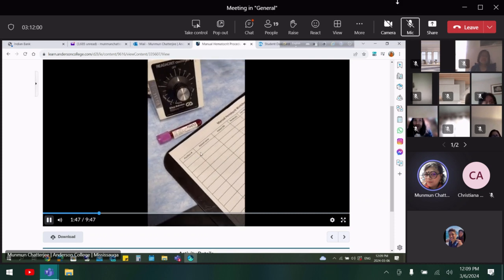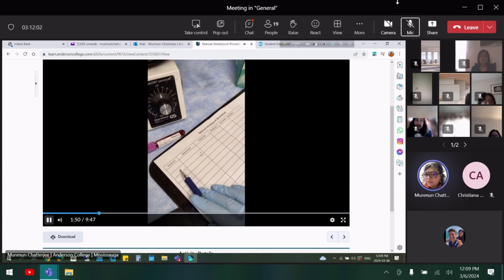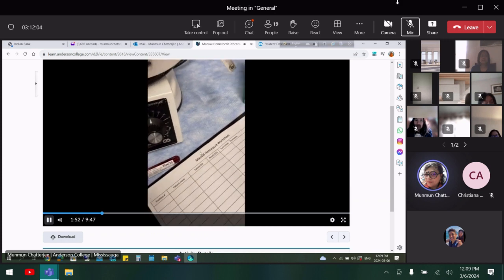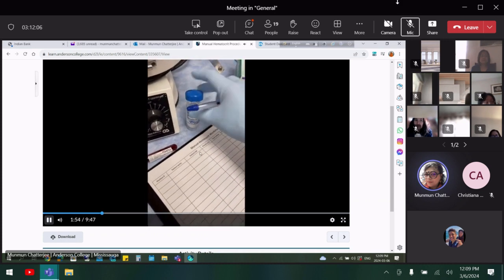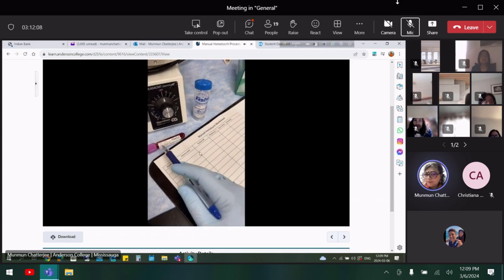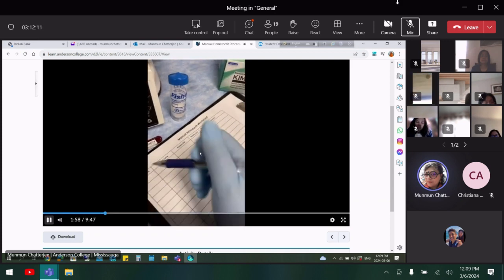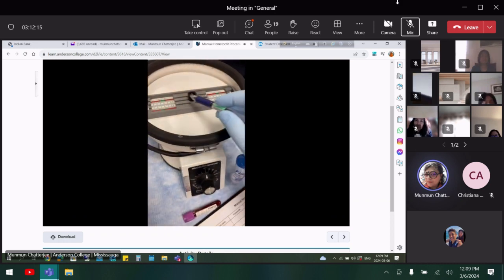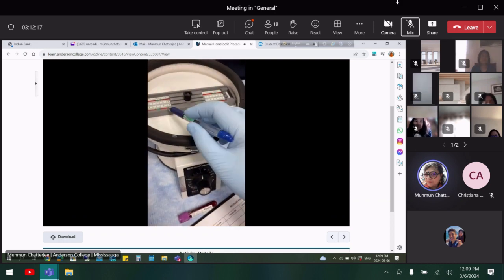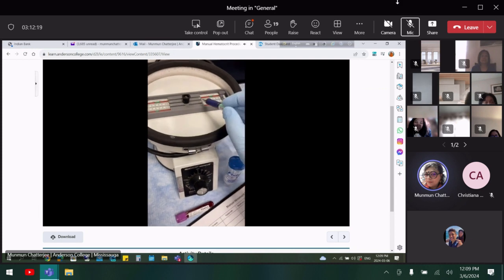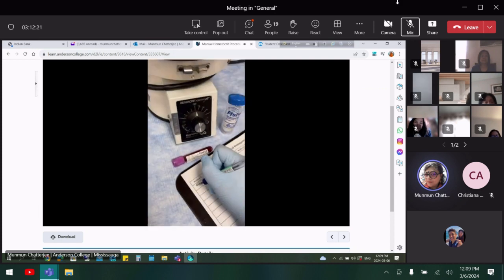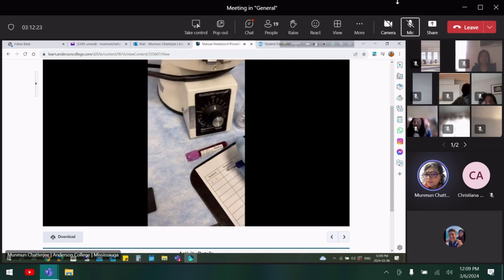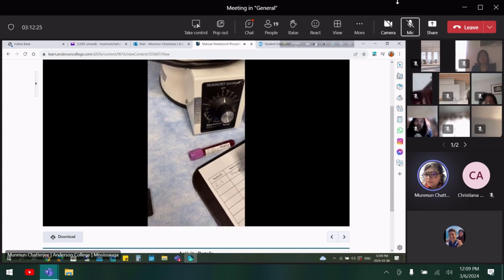Writing our patient information on our worksheet is really helpful because we can't label our capillary tubes, they're too small. So we take our patient information directly off the primary label, and indicate which positions in this rotor we are going to put our sample. In this instance, I'll be using section 2 and section 5. So I write position 2 and 5, and then the patient's name.